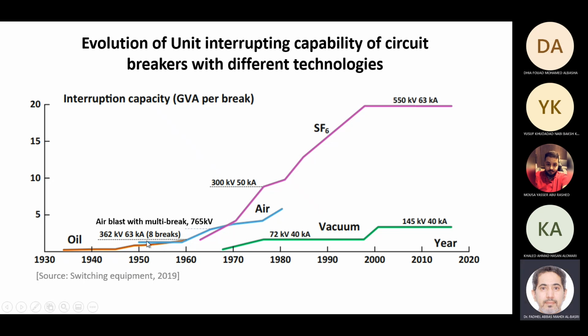So then they have air blast, air blast with multi-break points. Oil breakers became almost extinct in the 1960s. It's not used, so there's no point in explaining it to you today, if it's not used anymore. Air blast breakers were then used, where air is used as the insulation media. They have a limited breaking capacity. Still, we have a limited breaking capacity.